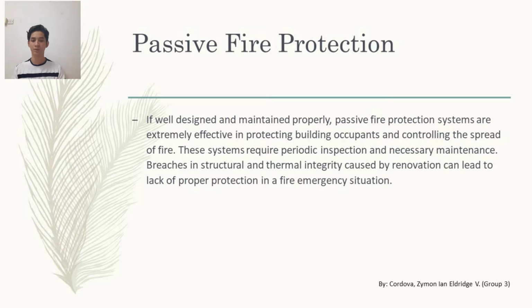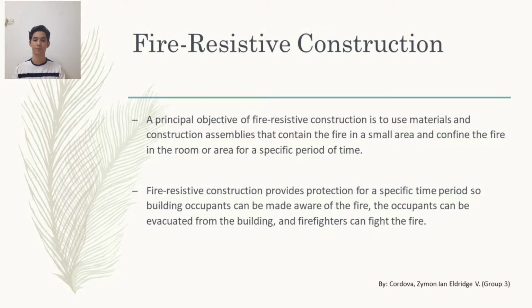Breaches in structural and thermal integrity caused by renovation can lead to the lack of proper protection in fire emergency situations. Fire resistive construction. A principal objective of fire resistive construction is to use materials and construction assemblies that contain the fire in a small area and confine the fire in the room or area for a specific period of time. Fire resistive construction provides protection for a specific time period so building occupants can be made aware of the fire, the occupants can be evacuated from the building, and firefighters can fight the fire.